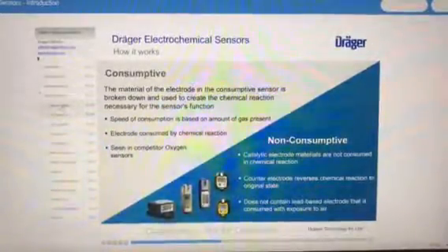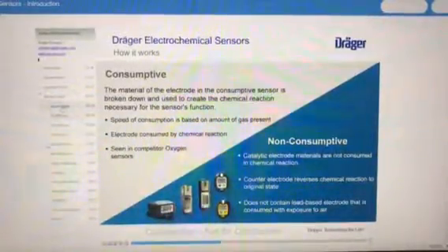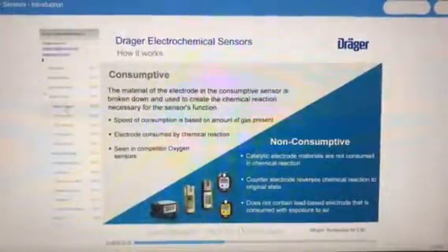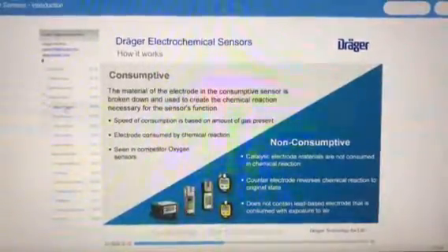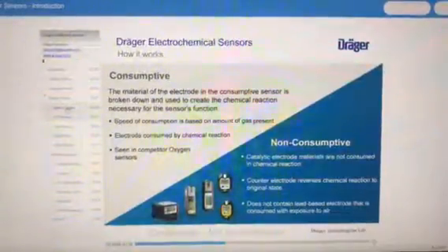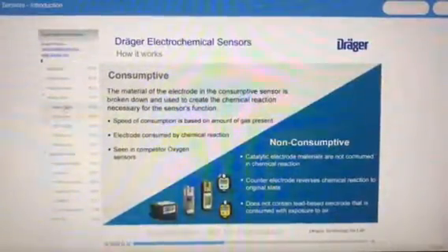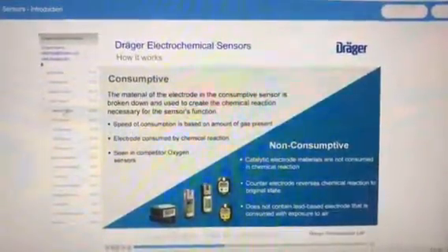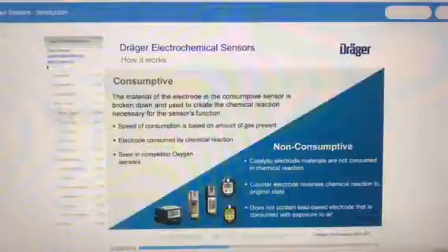The Draeger oxygen sensor is unique in that it does not contain a lead-based electrode that gets consumed with exposure to normal air. The oxygen sensors manufactured by some of Draeger's competitors are made with a lead-based electrode, and they begin to degrade immediately after the first use. Draeger's electrochemical sensors can be found in your X-am 2500, 5000, 5600, and 7000 instruments.